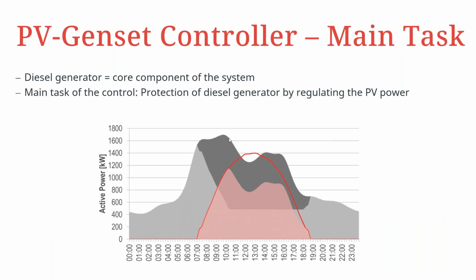Now, continuing, we're going to delve more into the PV-Genset controller and its main task, and how a system can be designed using the information that will be given to us subsequently. The main task of the PV system controller is to protect the diesel generator, like I mentioned in the previous slide, because if it doesn't protect it, there's a high possibility of negative feedback depending on the injection of PV in the system.